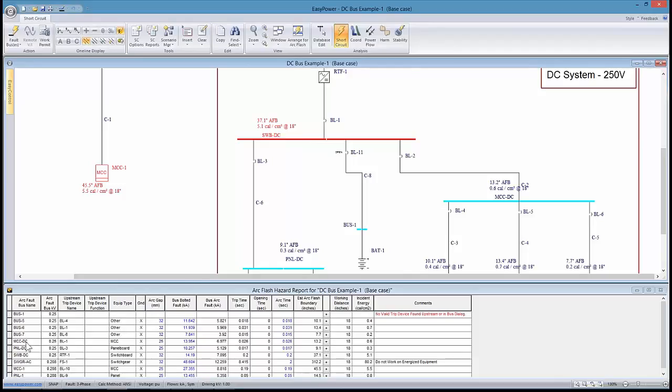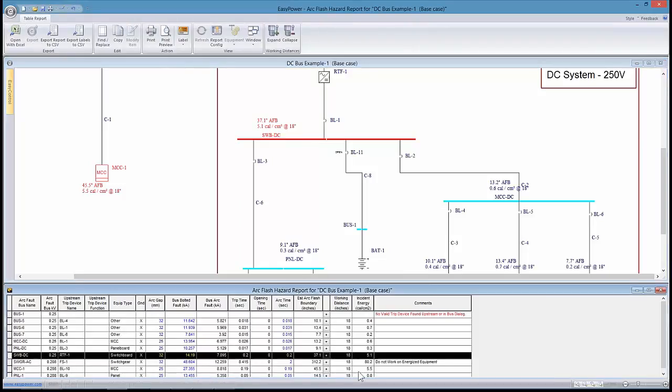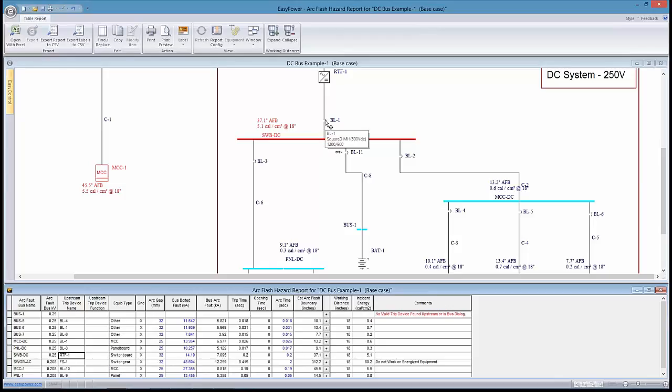So if I come back down here and look now, I see that the protective unit in play is RTF1, which means that the rectifier protection now is taking place. So the question is, where is this particular breaker? Why isn't this playing into my protection scheme?